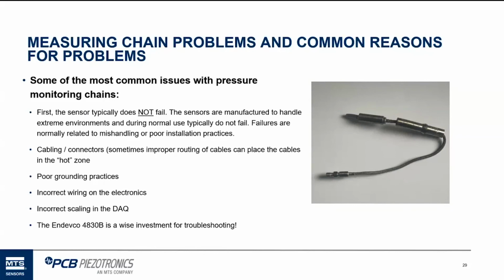Problems with the measuring chain, without the sensors, are usually related to grounding. The wiring is wrong on the charge amplifier. Sometimes people tend to mix up the ground on there. And then another big problem I've run into is the scaling within the data acquisition or CDMS system. The scaling's set too high, so they don't see anything in the bottom of the display. There's no data. So you fix the scaling, make it where it actually should be, you're going to see data. So that Endevco 4830B is a really wise investment for troubleshooting a system, and it's not very expensive either. It's a great tool. I use one when I go in the field sometimes to test the system for a customer.